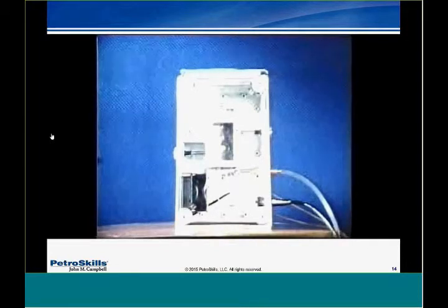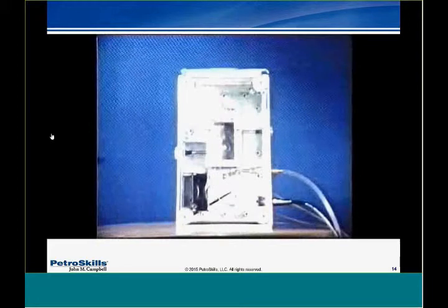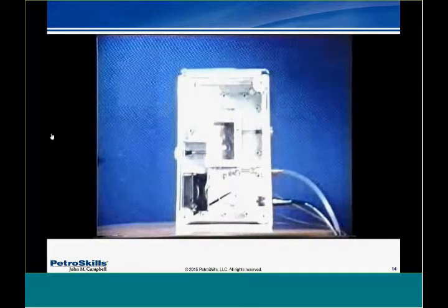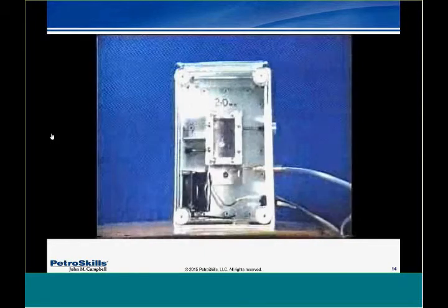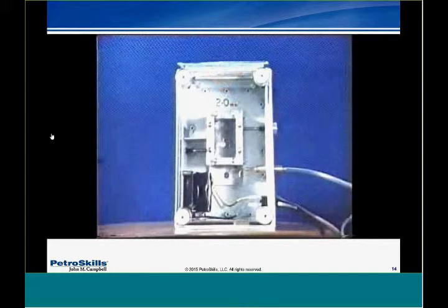There is a flammable mixture of gas and air in both the flame-proof enclosure and the surrounding box. Now, a spark. Since the flame-proof enclosure is effective in containing the explosion, the flammable mixture in the large box does not ignite. But with the gap enlarged to 2 millimeters instead of 0.8, a spark instigates an explosion that does propagate out of the flame-proof enclosure into the surrounding box.